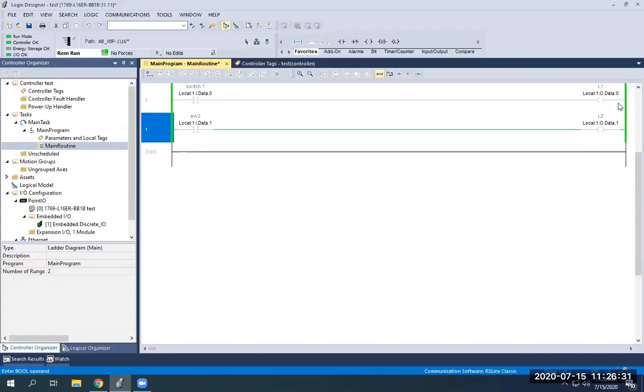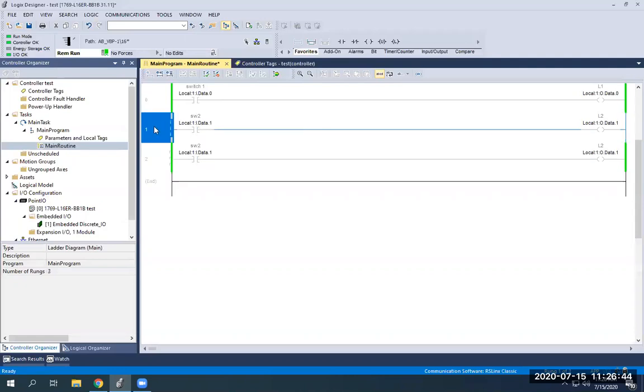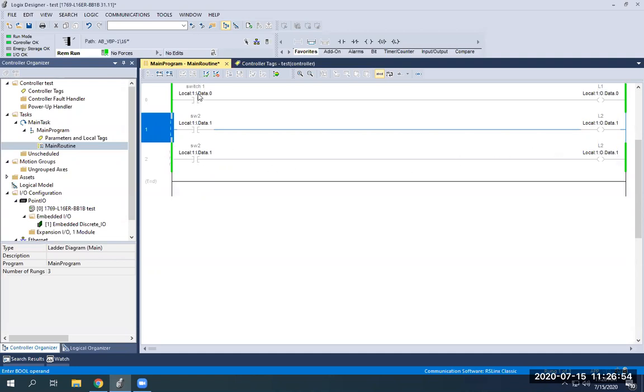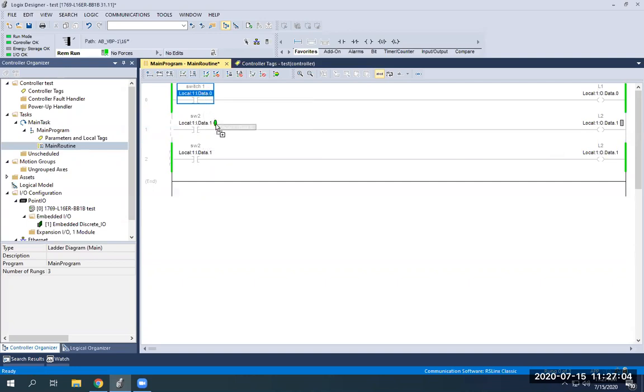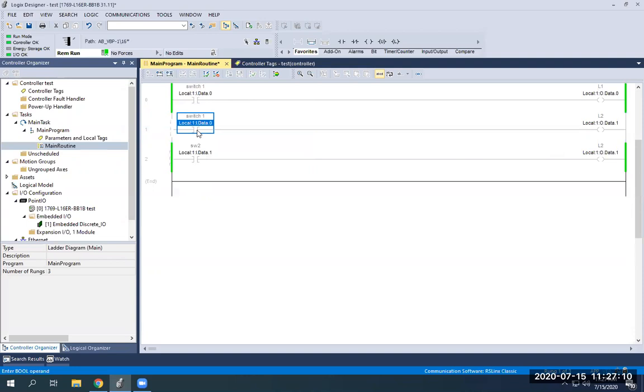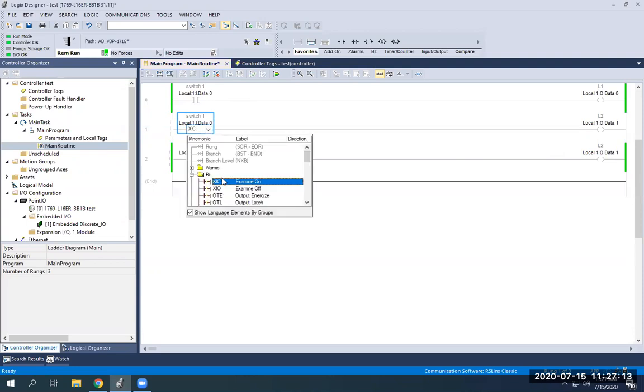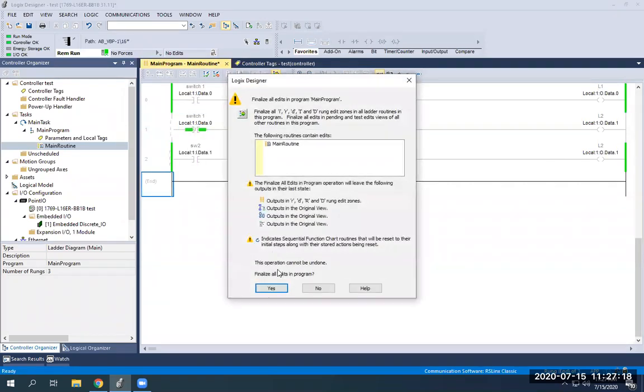Now I've done XICs and outputs. Just to mix it up a little bit, I'm going to show you guys how to change this to an XIO and then change this one also to switch one. Quick way to do that is you double-click on the line to make any edits. Now it'll show this duplicate down here, but this one is just going to be a reject. Once you finalize, this will go away. It's just showing you what you had on the line before. You can actually click on the address. Don't click on the description or the device. Click, hold, and drag down here until it's highlighted and let go. Now it copied the data to it. Then if you want to change the device, you double-click on the device. Now I can just change this C to an O, make it an XIO, and then finalize my edits.